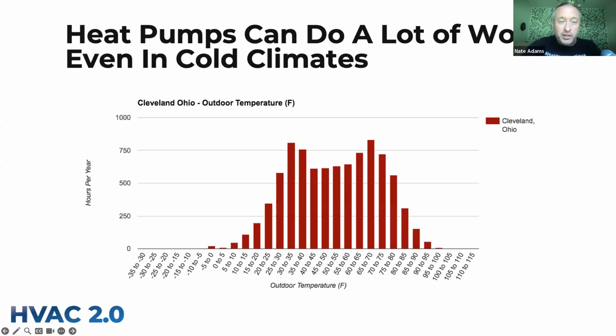750 hours is roughly a month. If you look at one of the tallest bins on the left, the 30 to 35 range, that's right around 0 Celsius, and in Cleveland we spend about a month in that bin. That is really good heat pump territory. Most heat pumps are still working really well down to freezing and a bit below. So even though Cleveland is considered a very cold climate, the vast majority of the work can actually be done with a heat pump, even in a hybrid.